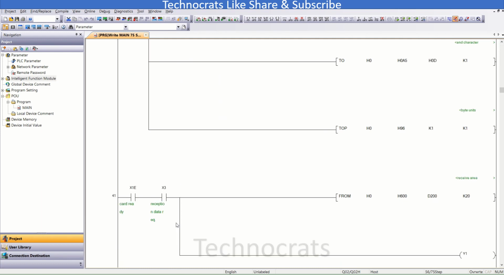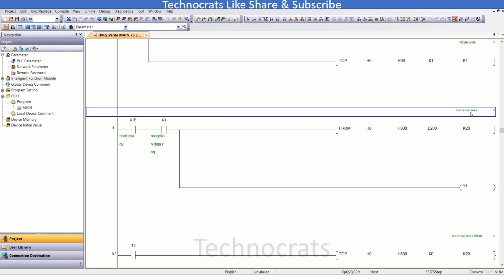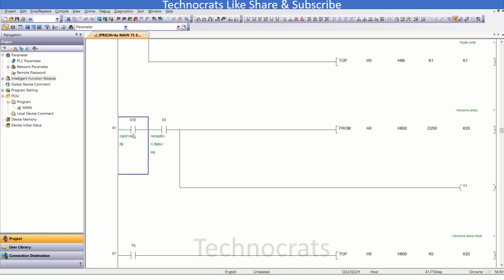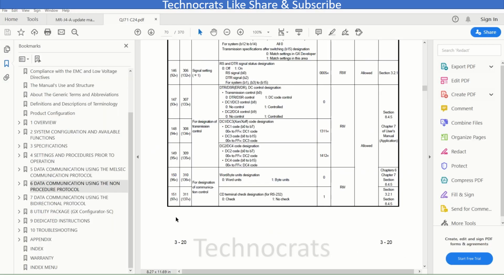Now this is the receive area, in which area I want to receive the data coming from the barcode scanner or any of the scanners you are using. So X1E is the card ready signal. X3 is reception data request, or you can say when the data is coming to the card, this X3 will turn on. So the FROM instruction is used, because I want to read the data from the card into the PLC. So H0 is again the same. H600 is a buffer. So let's see what H600 is.